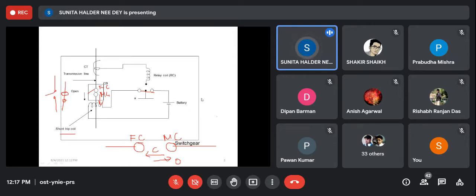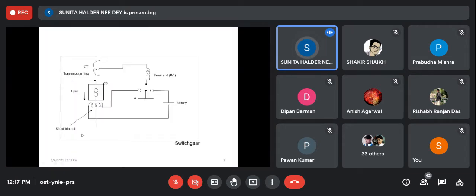So actually this total system is called switchgear. In switchgear, there is a circuit breaker and a relay. The study about the relay is generally called protection. Nowadays this may be different, but if you see the standard books written in the past, they are generally written on the protection system. Protection system actually means the relaying of a power system. Okay. So providing protection using a relay is called relaying or protection system. Understood?